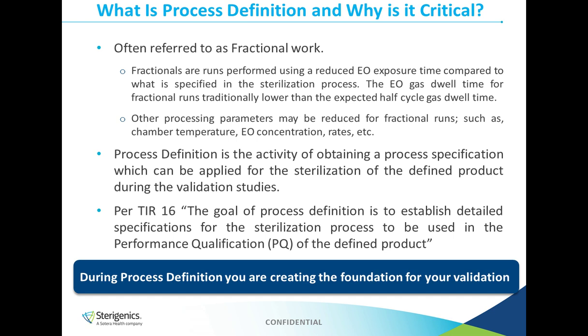Now, ISO 11135 says process definition is the activity of obtaining a process specification which can be applied to the sterilization of the defined product during validation studies. And the TIR also says the goal of process definition is to establish a detailed specification for the sterilization process to be used in performance qualification, or PQ, of the defined product. So to sum all that information up, during process definition, you're creating the foundation of your validation. This is why it is so critical.